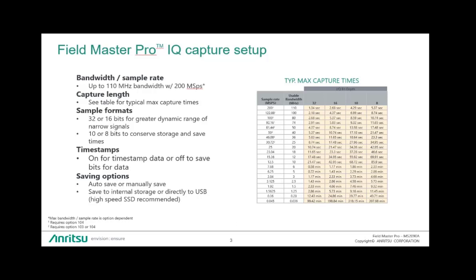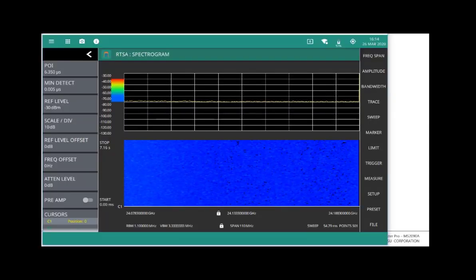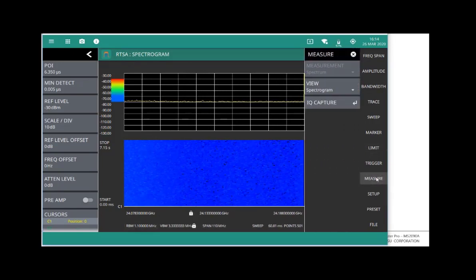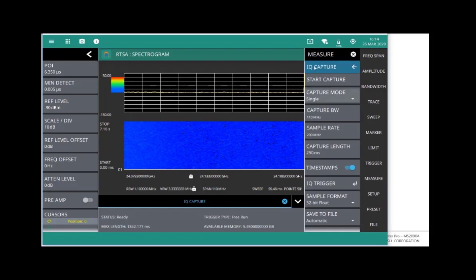So I'm going to actually open up, I'm connected to an instrument here remotely. I'm going to open up our IQ menus and show you a little bit about what we have here. So when I open up the menu, my IQ capture table opens up here. Before I start the capture, I want to check my setup. I can set up the instrument to capture either single or continuous or streaming. We're going to talk about streaming in a separate video.